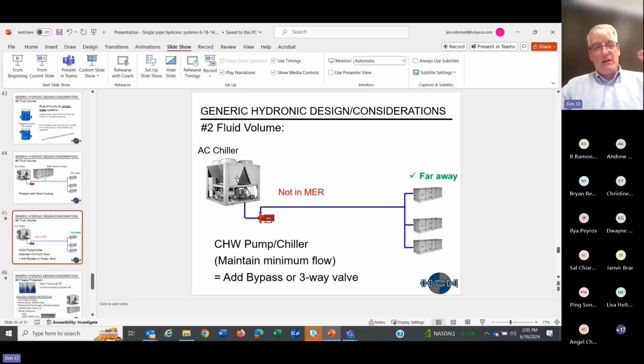So that 50 GPM of water can flow out through the chiller, and just using numbers, 40 GPM can flow through your coils, but then you'll have 10 GPM bypassing and coming back to the chiller. I just want to point out that you don't want that bypass of 10 GPM in the mechanical room or close by the chiller, because you'll end up having recirculation, short cycling, et cetera, of the chiller. You want to send that slug or mass of water out into your system, a distance away.